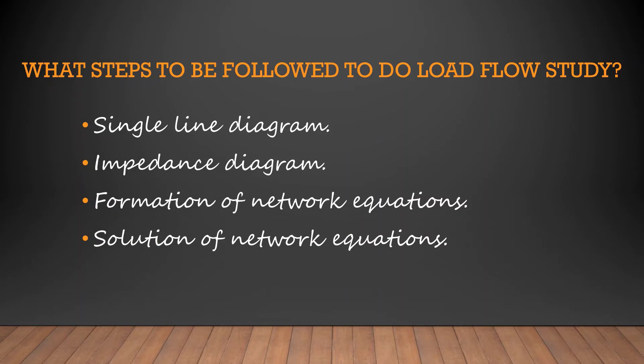The next step is the solution of network equations. This is the most important point to understand. The solution of the network equations — algebraic equations describing the power system — is based on an iterative technique, simply because of their non-linearity. The solution must satisfy Kirchhoff's laws; that is, the algebraic sum of all flows at a bus must equal zero. One or other of these laws is used as a test for convergence of the solution in the iterative computational method.